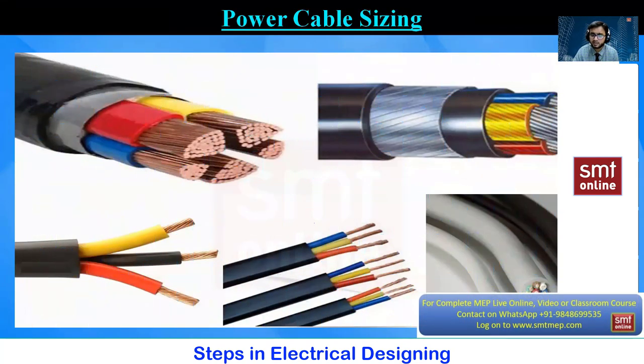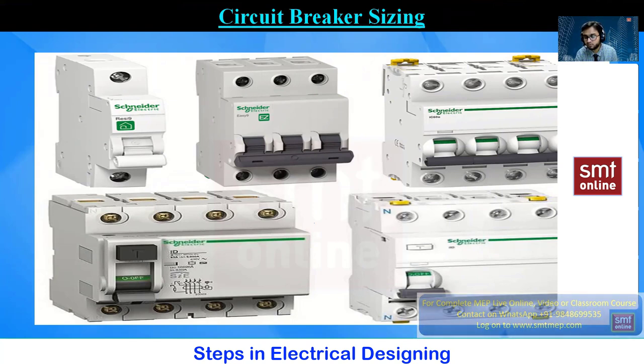For emergencies, diesel generators are used. For commercial projects like corporate offices, a UPS and battery supply supplement the main transformer supply. For power cable sizing, we consider the type of conductor, insulation, armored or unarmored, number of cores, and cable shape — flat or round. Circuit breakers come in different types classified by load: single pole, double pole, three pole, four pole, and by curve type — all of which will be covered.